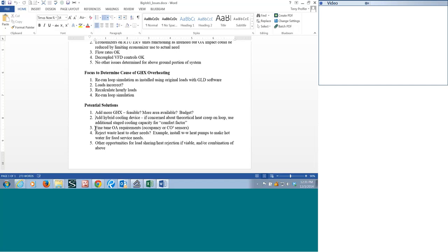And then, of course, by code, if you get too hot or too cold in outside air temperature, you can shut your economizer down. But we find a lot of times ERV enthalpy wheel equipment is miscontrolled or it's malfunctioning. And when it's supposed to be using the energy recovery ventilation component, quite often they're getting too much outside air mixed in, and it's exceeding code, and it's just putting much more load on the ground loop than is necessary.